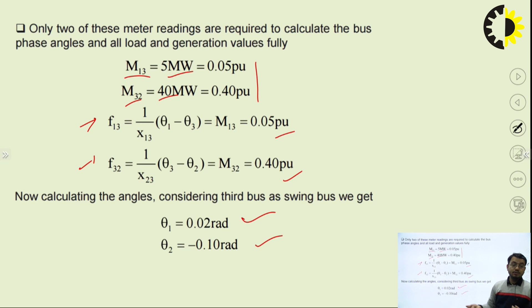Right? Now if you want to have state estimation, what do you require? A procedure that uses the information available from all the 3 meters to produce the best estimate of the actual angles, line flows and the bus load and generation. We require only these values. So we have 3 meters providing us with a set of redundant readings with which to estimate 2 states, that is theta 1 and theta 2. These are basically the states being determined over here. We say that the readings are redundant since, as we saw earlier, only 2 readings are necessary to calculate theta 1 and theta 2, and the other reading is always extra.